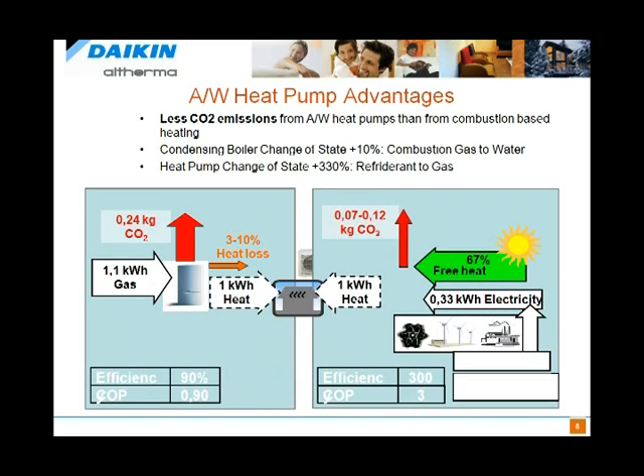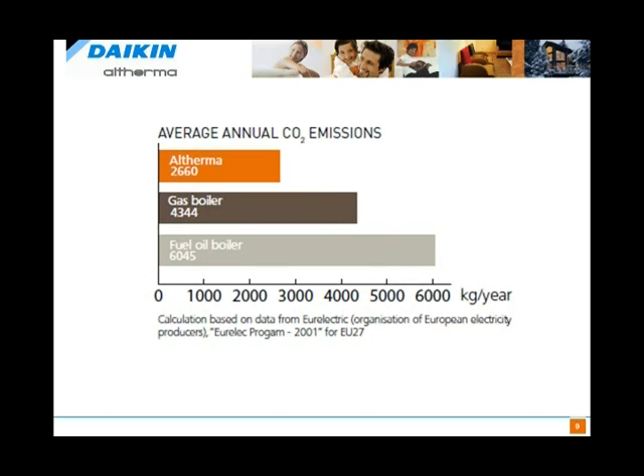We're using a COP of 3 here, which would be about the minimum you'd be able to generate in our Mediterranean climate zone in California. More typically, we're in the 3.7 to 4.3 COP in California Mediterranean zones. So as a result of this, the altherma in terms of CO2 emissions is substantially less than gas boilers and a lot less than a fuel oil boiler, even when you account for natural gas being burned in the utility and transmission losses. Still, the boosting factor of the heat pump creates a low emission device.